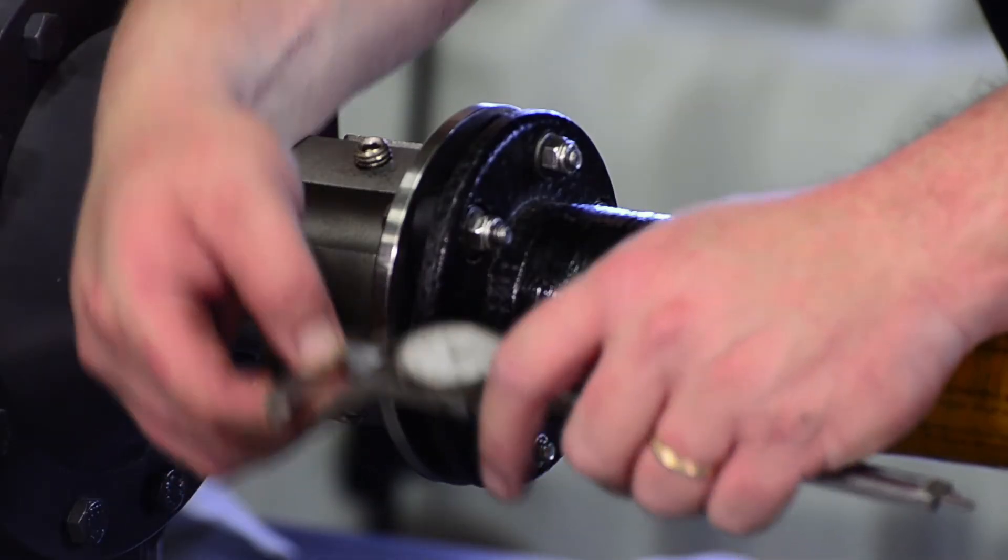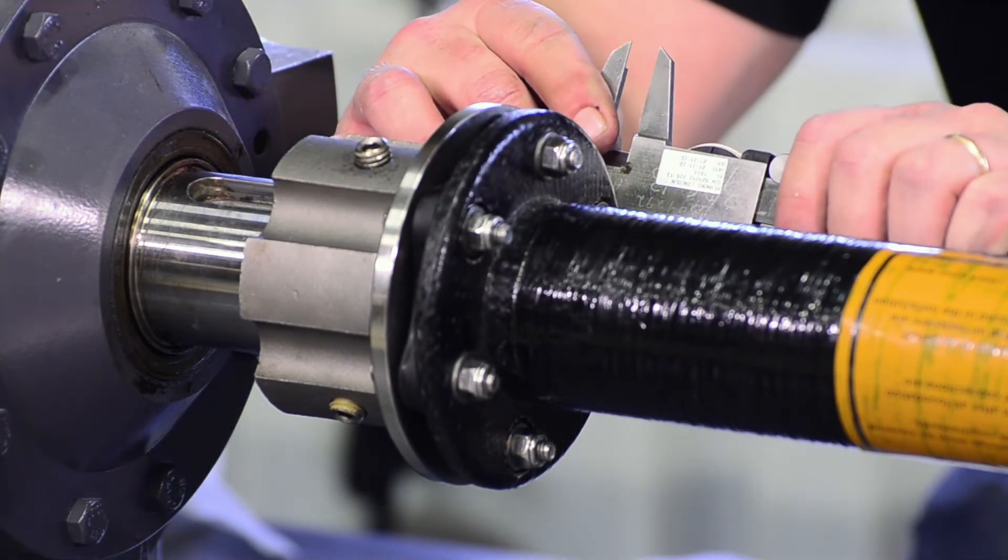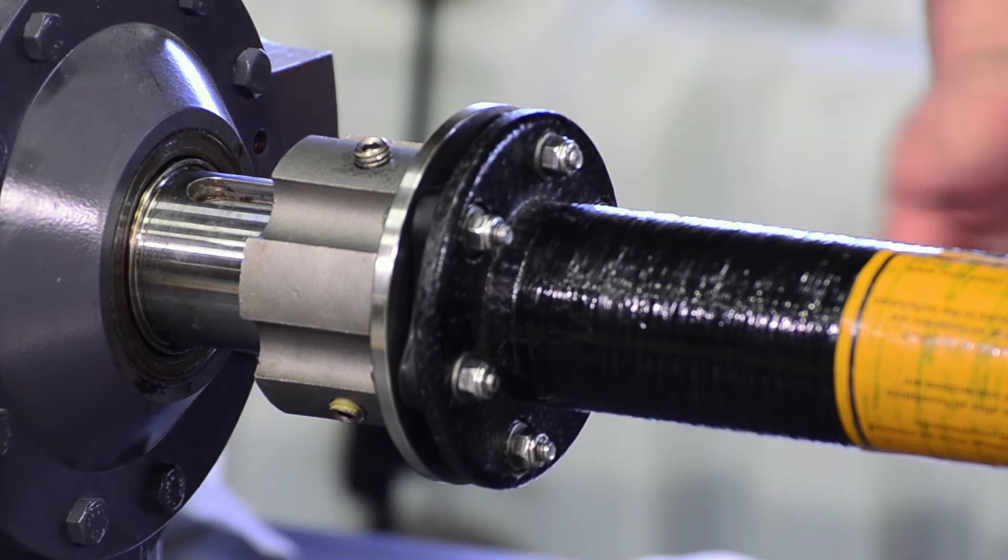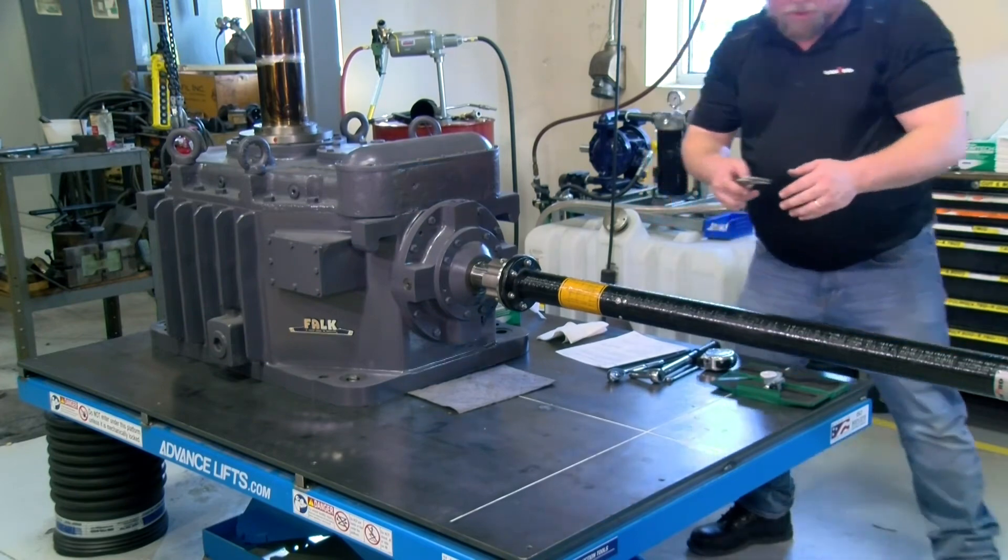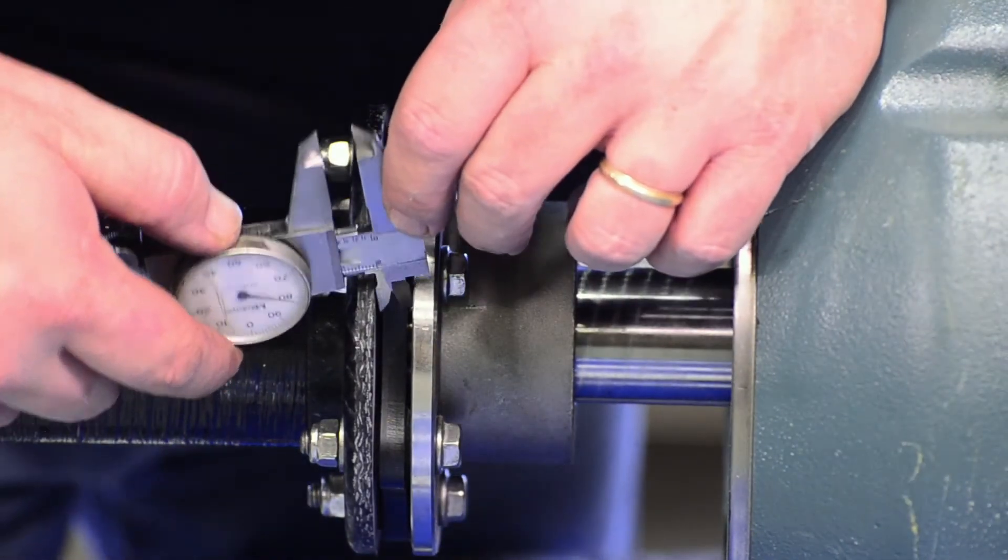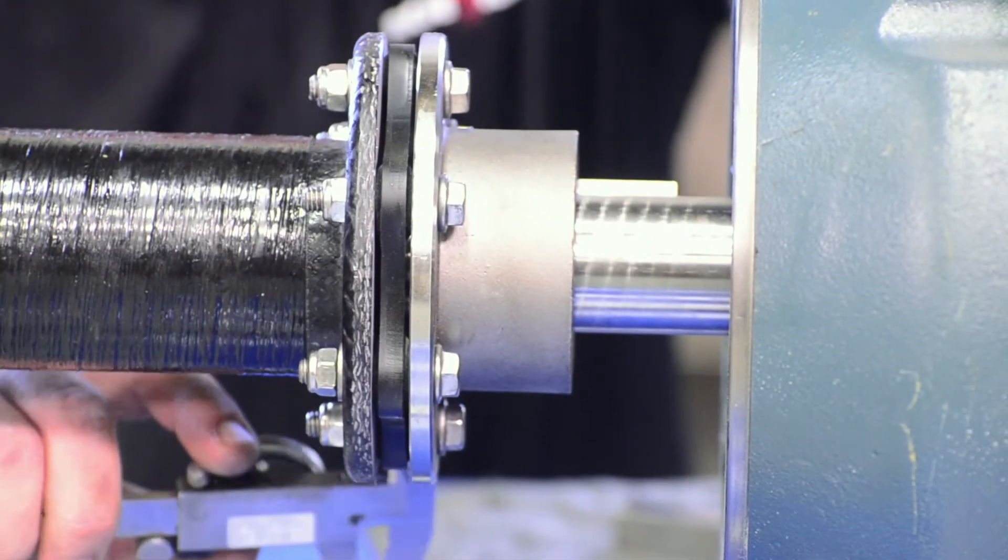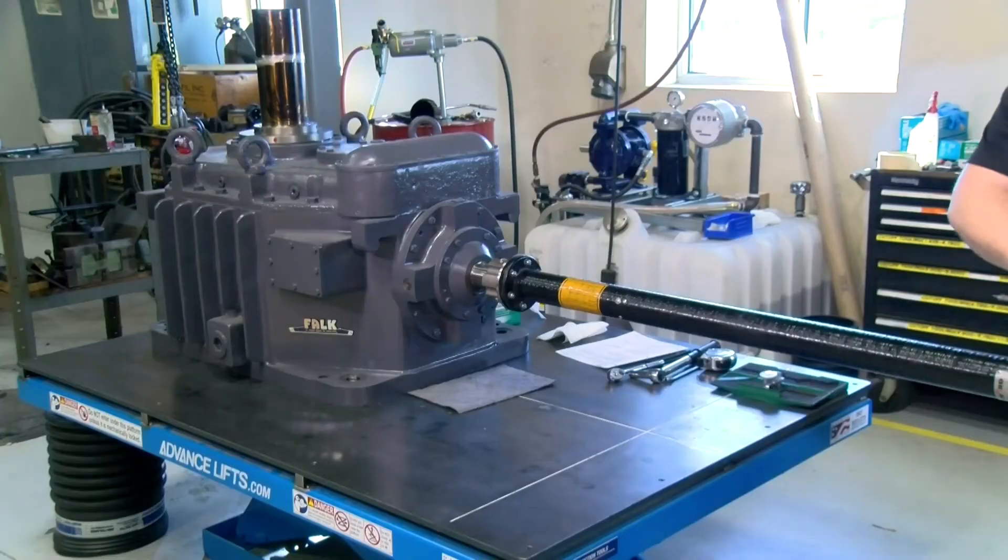To check axial alignment, a caliper should be used to measure the gap between the spacer and hub flanges on each coupling end. Without rotating the coupling, take four readings around the perimeter at 90 degree intervals as shown. For each coupling end, compare the average of the four readings to the specified axial alignment limit. If this calculated average exceeds the specified limit, the corresponding hub must be repositioned and axial alignment reverified.